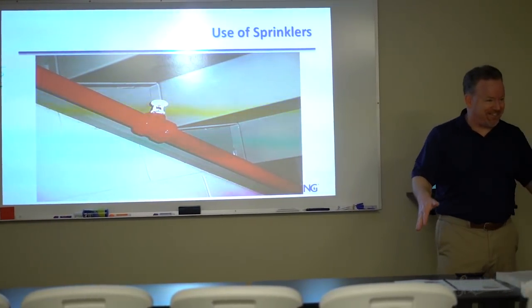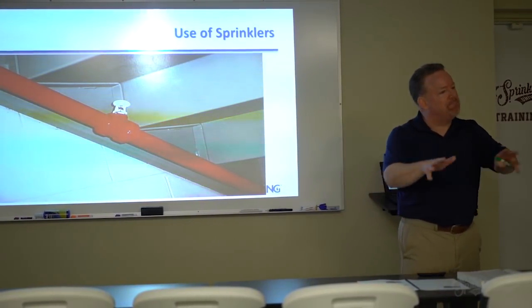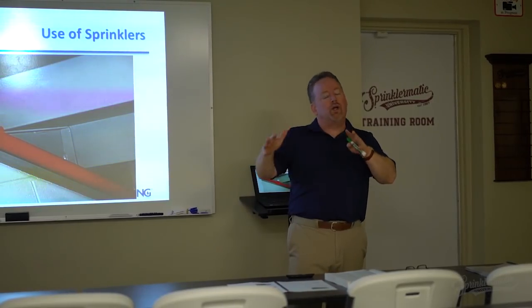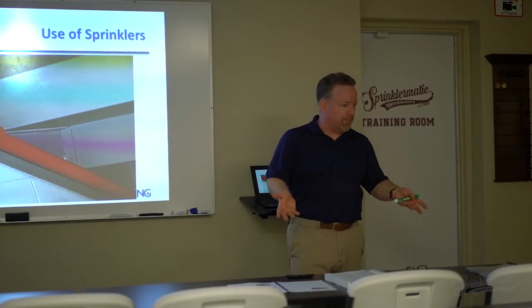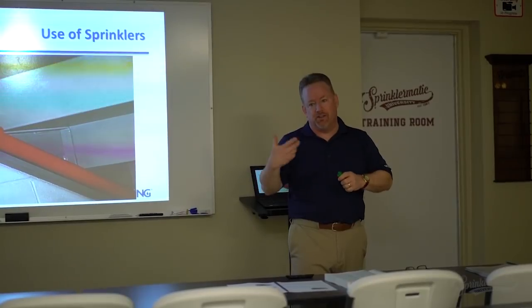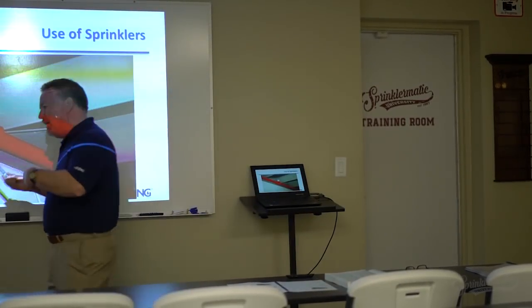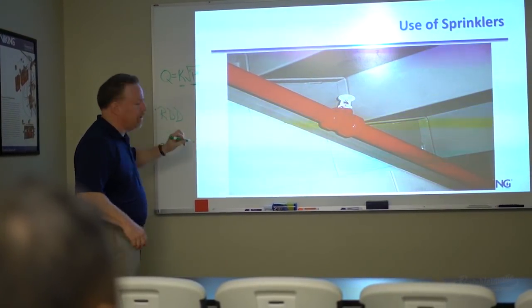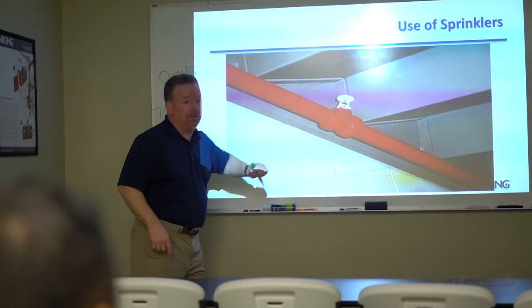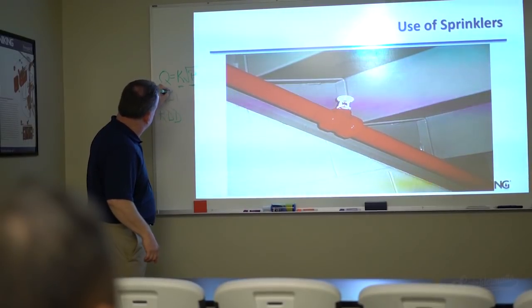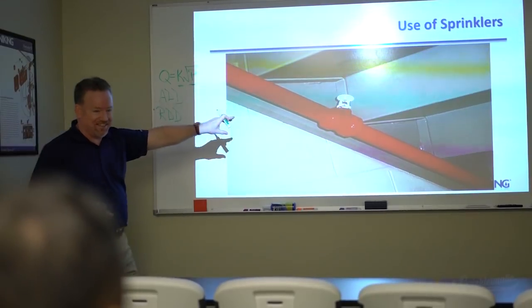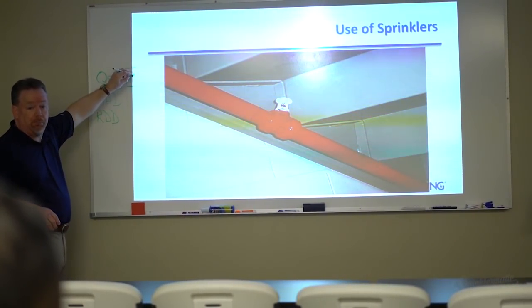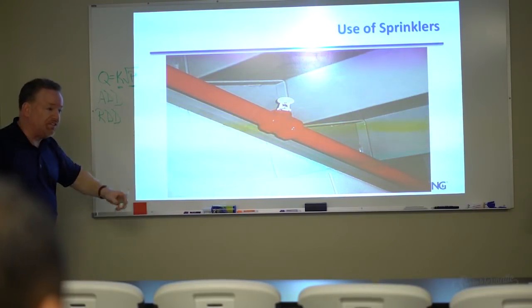The amount of water required is based on what's underneath the sprinkler. Items like tables burn at a certain rate, requiring a certain amount of water to control the fire. That's called the Required Delivered Density, or RDD. Fire labs have burned materials representative of a given space, and that establishes the RDD. The sprinkler then has an ADD — Actual Delivered Density — which is the water sprayed out based on K times the square root of P.